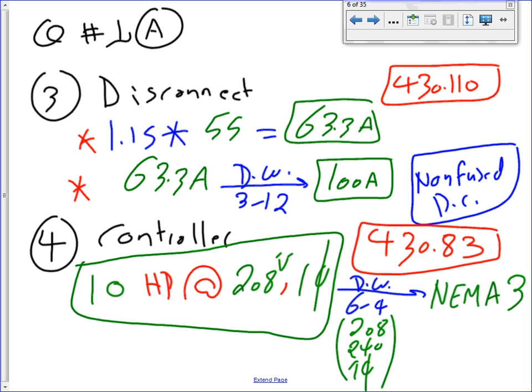And the table is easy. You guys go under the table that says 240. And under 10 horsepower, it cross-references itself with NEMA 3. It will give you NEMA 0, NEMA 00, NEMA 0, NEMA 1, NEMA 2, NEMA 3 sizes of these contactors. That's how they size them.